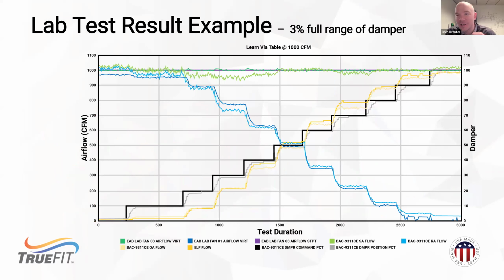We've had a lot of chances to install TrueFit across the country. One of them was the University of Texas Medical Branch down in Houston, where they have class 3 and 4 containment labs for researching things like Ebola and infectious diseases, places we probably really don't want to be as people or occupants in those buildings. But in order to qualify to be on their networks, we had to go through an independent test at a certified lab that they use for all of their airflow measurement devices and balancing. And at the end of the day, what came out of that certification was that TrueFit is within 3% of airflow at the full range of damper positions, supply, return, and OA.